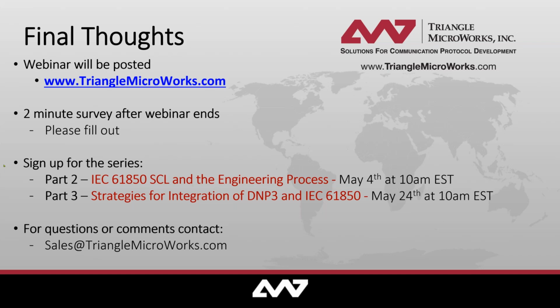Well, I think one of the key elements is, like it has been answered already, the engineering process that we will discuss in the next webinar. That's one key feature. It always depends what you call a digital substation, but commonly we understand digital substations where we have merging units that do the analog to digital conversion directly, and for that we have the sampled value service.